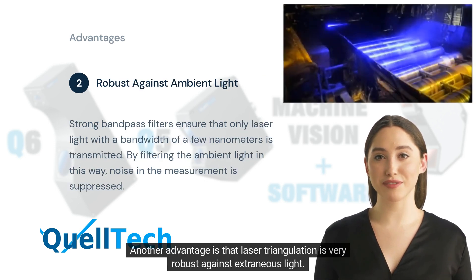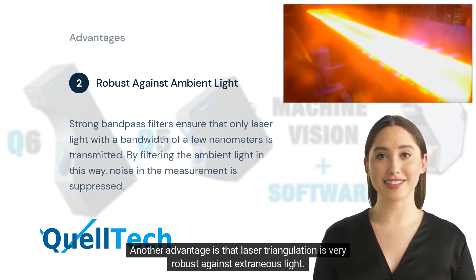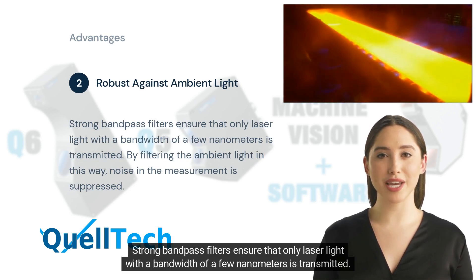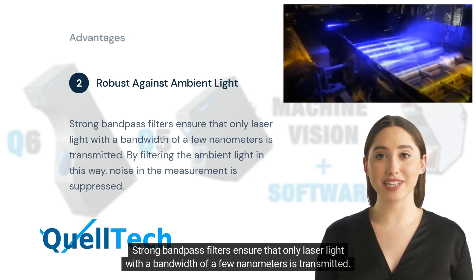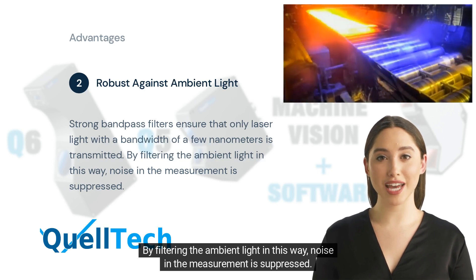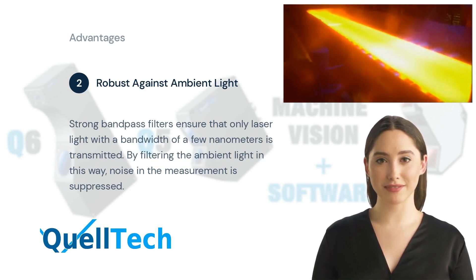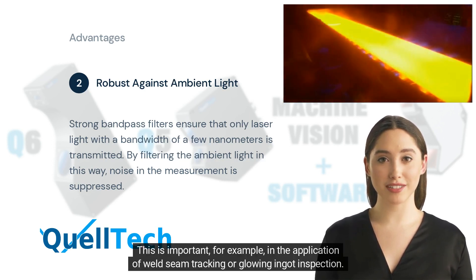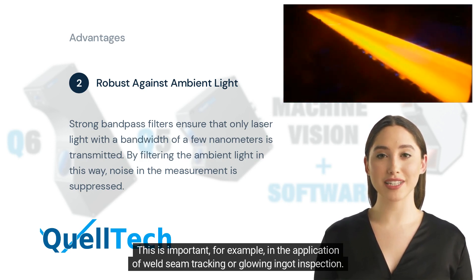Another advantage is that laser triangulation is very robust against extraneous light. Strong bandpass filters ensure that only laser light with a bandwidth of a few nanometers is transmitted. By filtering the ambient light in this way, noise in the measurement is suppressed. This is important, for example, in the application of weld seam tracking or glowing ingot inspection.